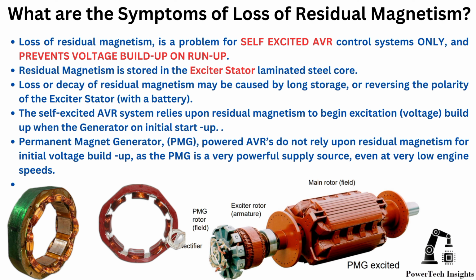Residual magnetism is stored in the exciter stator laminated steel core. Loss or decay of residual magnetism may be caused by long storage or reverse polarity of the exciter stator. The self-excited AVR system relies upon residual magnetism to begin excitation, and voltage builds up when the generator is initially started up. Permanent magnet generator (PMG) powered AVRs do not rely upon residual magnetism for initial voltage buildup, as the PMG is a very powerful supply source, even at very low engine speeds.